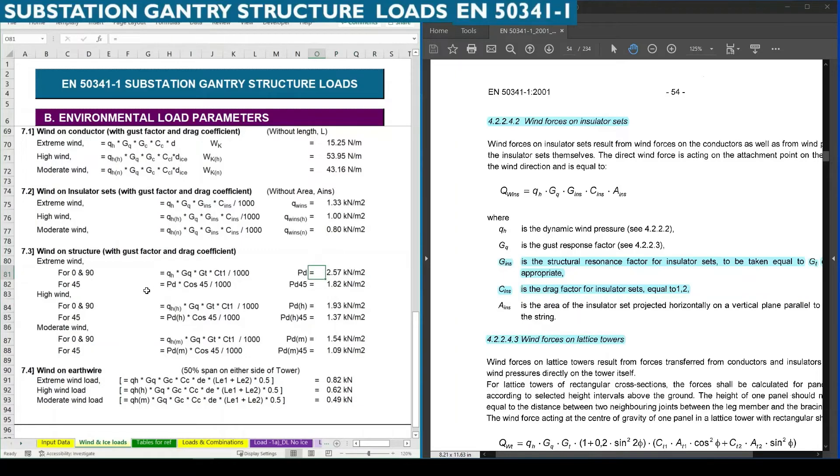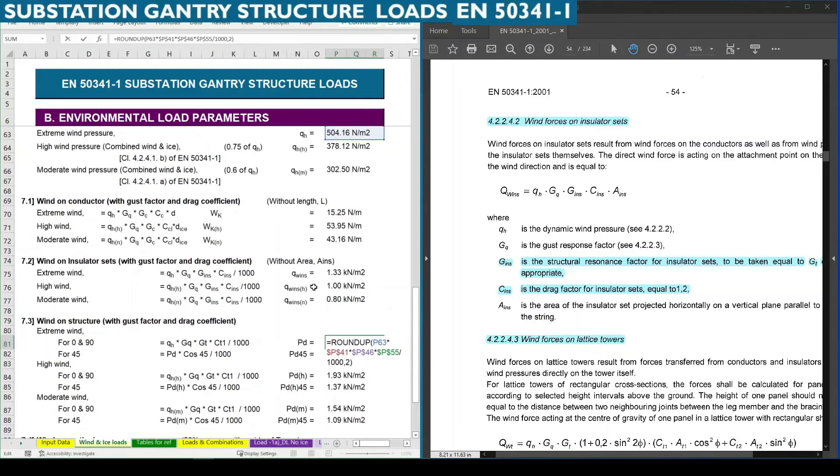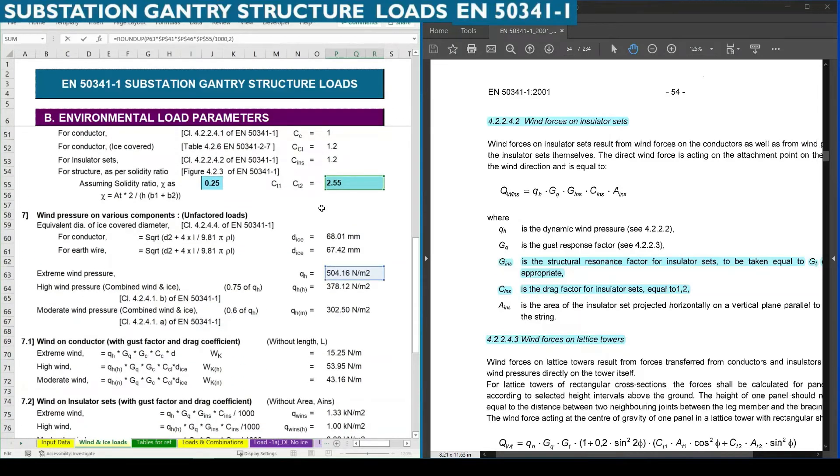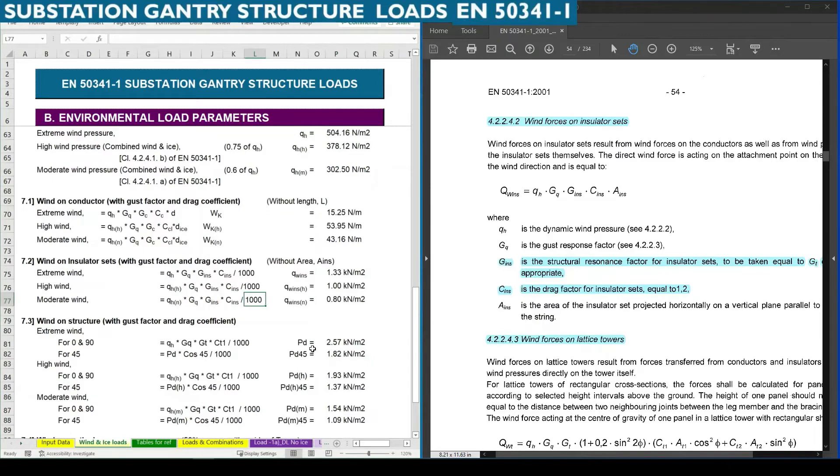Similar for wind on structure. Generally in European standard they calculate wind forces on structure in three directions. One is zero which is parallel to conductor, another is 90 which is perpendicular to conductor span, and another is 45 which is diagonal to conductor span. We are going to calculate the same way in three directions. Zero and ninety degree are the same, only the direction is going to change, magnitudes are same. So we are applying the drag coefficient which we already found as 2.55 using assumed solidity ratio of 0.25. Applying CT1 and GT into QH, we are getting the values for the formula.